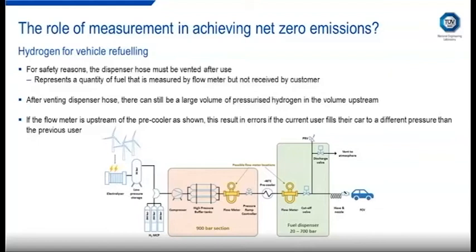The location of the flow meter also matters, so there are two locations shown on the diagram: upstream and downstream of the heat exchanger. Depending on where it's installed, the pressure and temperature conditions can be very different. You can imagine that the flow meter installed upstream of the heat exchanger will typically be around ambient temperature, whereas the one installed downstream can see temperature ranges of ambient down to -40 degrees C. So that has important implications for the measurement accuracy.